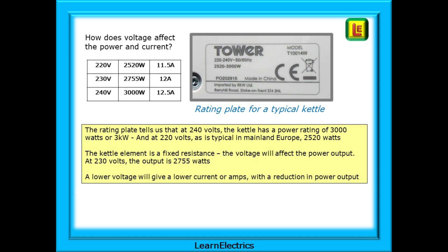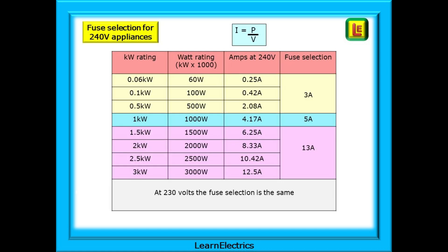For a given appliance, if the voltage increases the current will increase; reduce the voltage and the current and watts will decrease — we as users have no control over this. Take a 3 kilowatt kettle as an example: it is only 3 kilowatts at 240 volts and uses 12.5 amps. The rating plate tells us it will also function at 220 volts in mainland Europe, but will only consume 11.5 amps and the wattage will only be 2520 watts — it will take a little longer to boil the water. The table also shows the data for 230 volts. This is because the kettle element is a fixed resistance and we are changing the voltage: change the voltage, change the amps and change the watts. This table shows the fuse selections for different power or kilowatt ratings and the current flowing. The current at 230 volts will be fractionally smaller but the fuse selection will be the same.